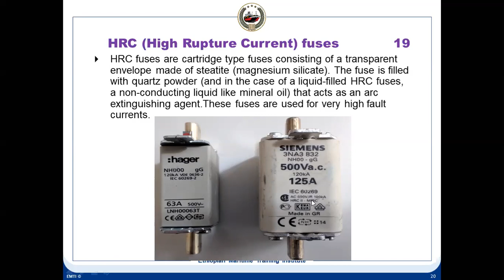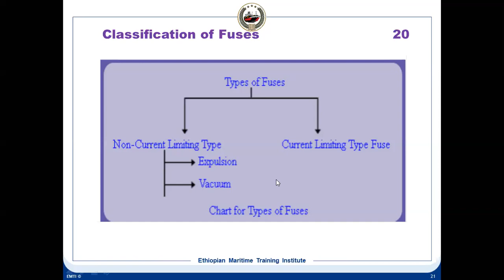high fault currents. So in this classification of fuses, it's called non-current limiting type and current limiting type, okay? So non-current limiting type is called expulsion type. Expulsion type means it has got a venting type. An expulsion fuse is a vented fuse in which the expulsion effect of the gas produced by the internal arcing, either alone or aided by another mechanism, results in current interruption. So this is interrupting the current in this way.